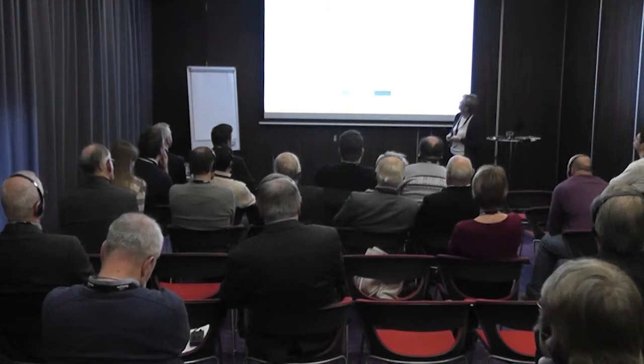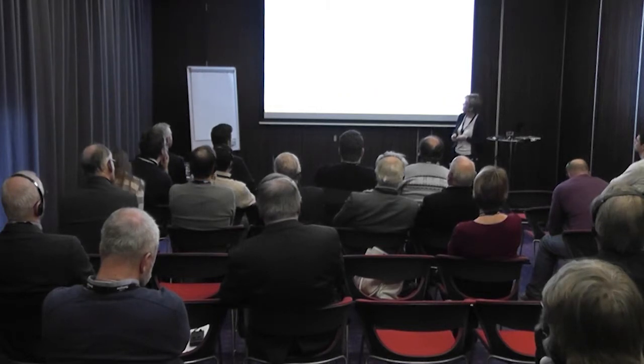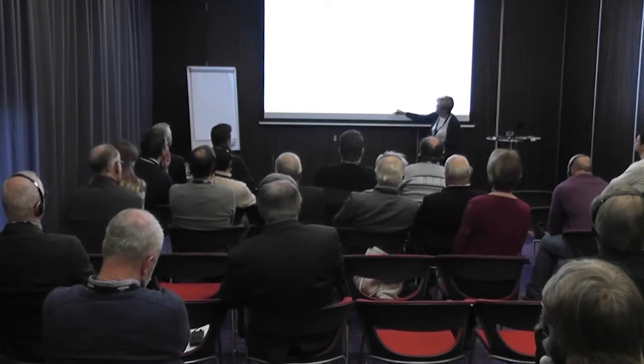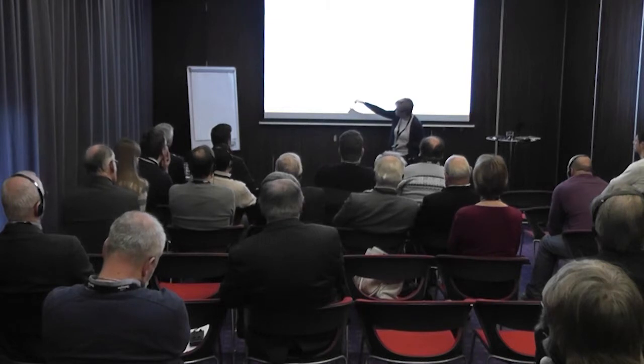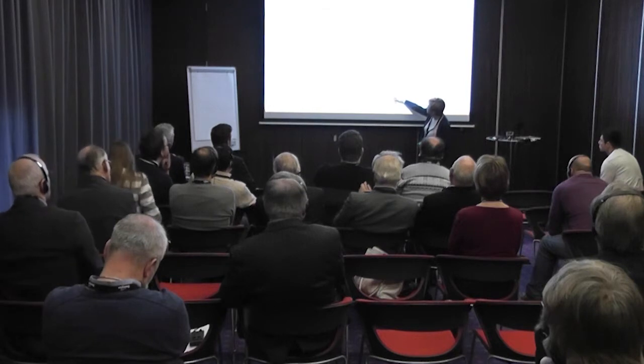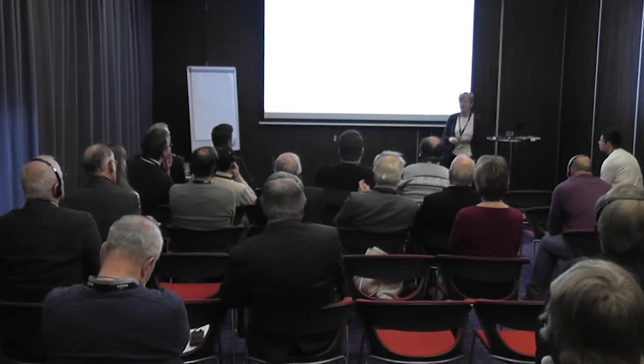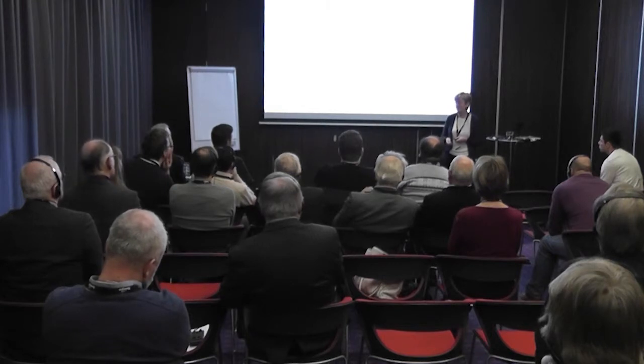So we also found some studies from the UK. A very interesting one. There they had documented the energy use per unit area for similar buildings as we are going into. It's a Cambridge Chemistry Building, Edinburgh Cancer Research Centre, and buildings like this. And what you see here, it's quite interesting high figures of energy. I think the lowest is 652 and the highest is 979 kilowatt hours per square meter. And that is quite extremely high, and it's about 10 times the target of this building in the nominal values.